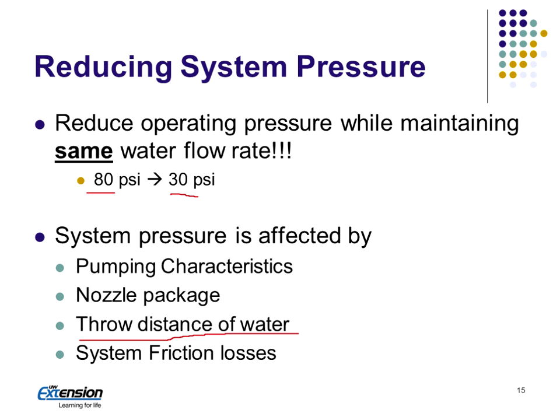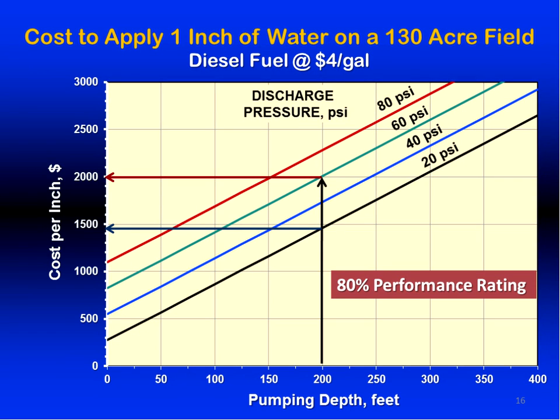But when we also reduce the pressure, it affects pumping characteristics. We'd have to change the nozzle package most often, and it can affect system friction losses if we allow the water flow to increase. And we'll explain why that happens sometimes.